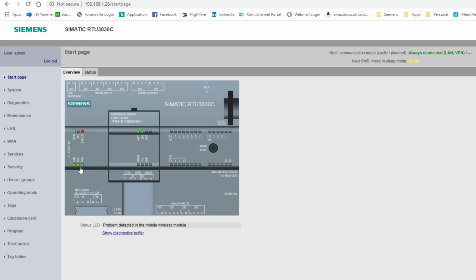I have a SIM card installed and my LAN is connected, and my HART is set up and it's polling away. I didn't set up the Modbus 485. There's separate connections, as you can see. The HART connections are here, and there is the 485, and this is my control power. So you have separate power connections, but this is if I want to power my loop powered instrument that has HART on, if it's a passive instrument stroke transmitter.